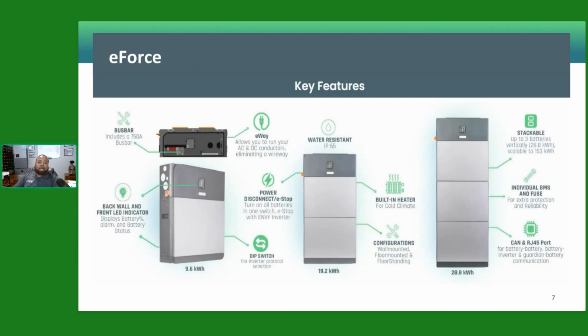We've used the technology from our E-Flex battery, which is the most installed in the market, with thousands of units out there, and developed it into a modular stackable battery, the E-Force. It's important to know the E-Force comes in modules from 9.6 kilowatt hours for one single module, 19.2 for 2 modules, and 28.8 kilowatt hours for additional modules.